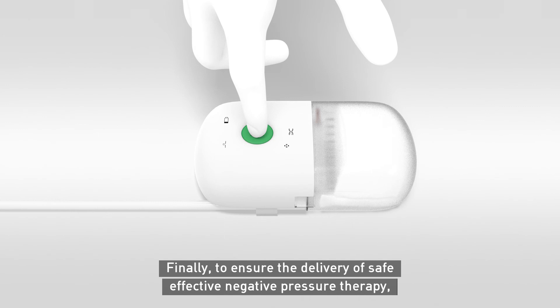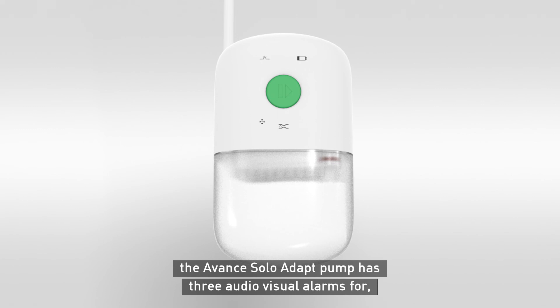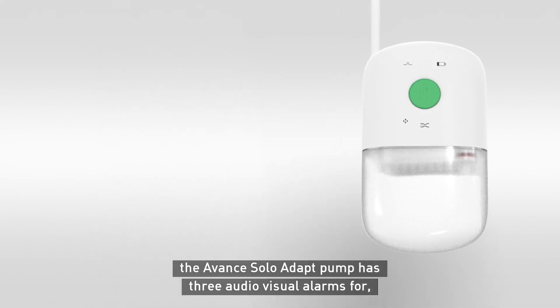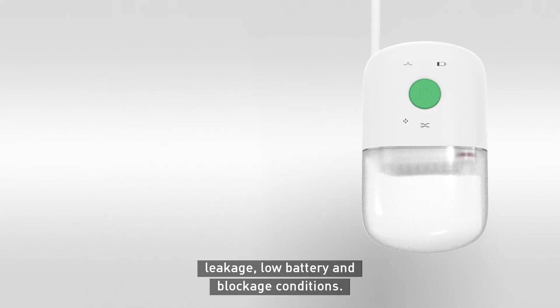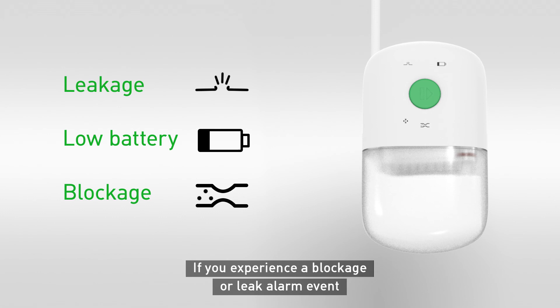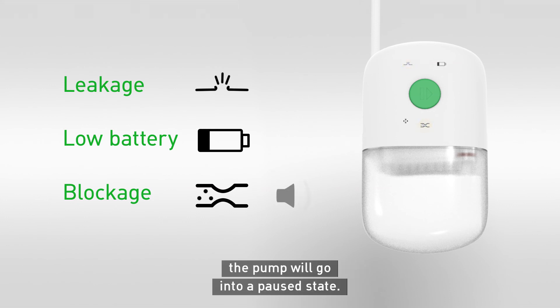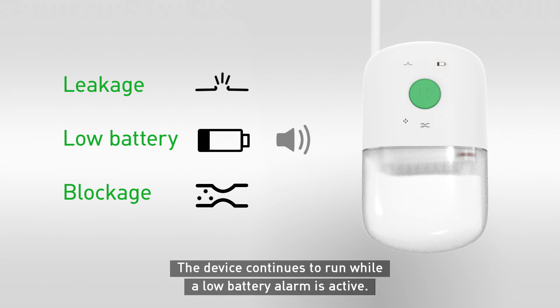Finally, to ensure the delivery of safe, effective negative pressure therapy, the Avance Solo Adapt pump has three audiovisual alarms for leakage, low battery, and blockage conditions. If you experience a blockage or leak alarm event, the system will issue an audible alarm and the associated alarm symbol will illuminate. The pump will go into a paused state. The device continues to run while a low battery alarm is active.